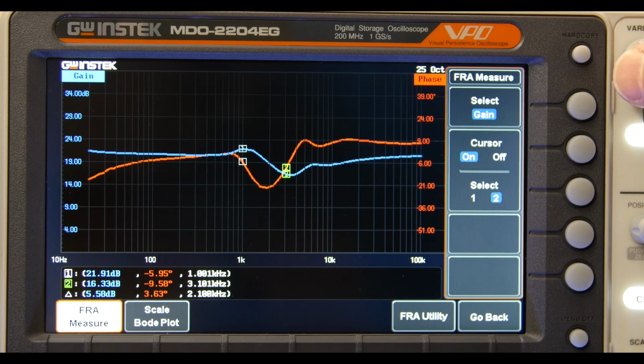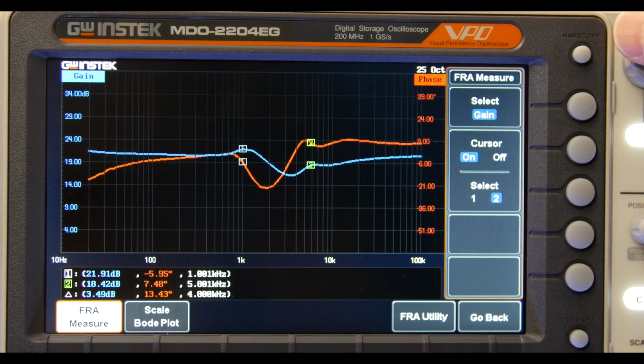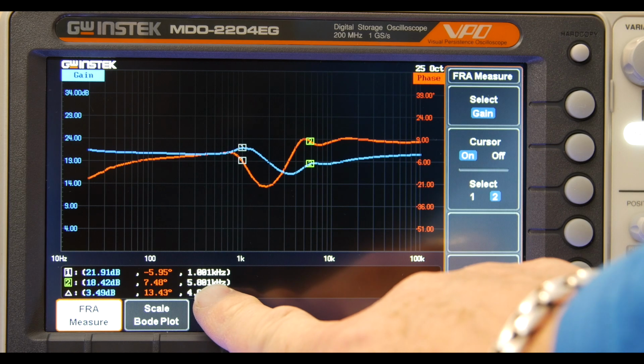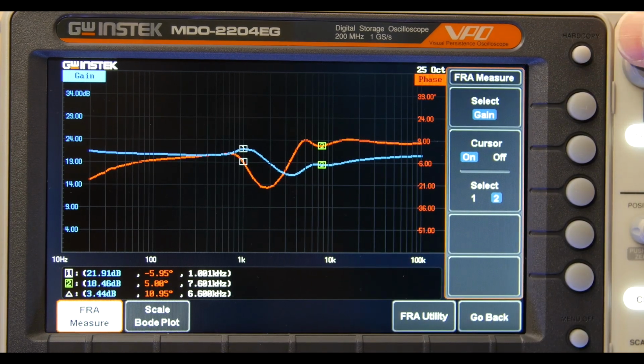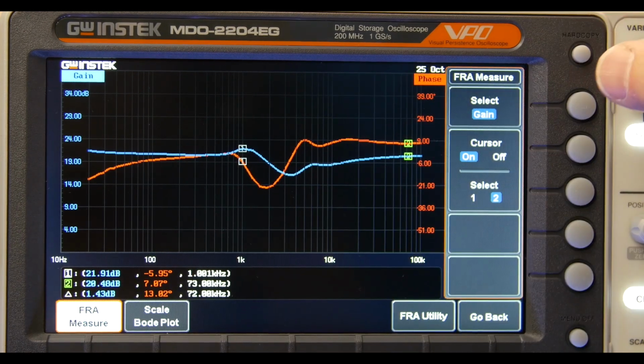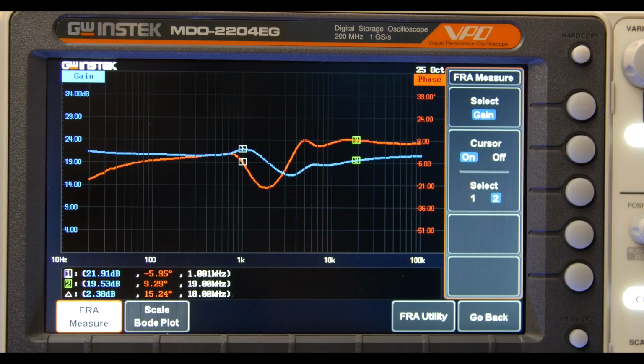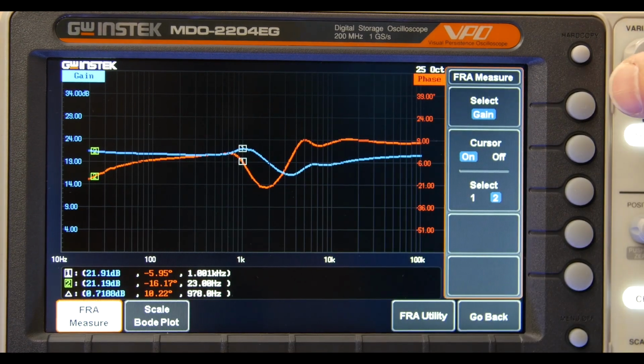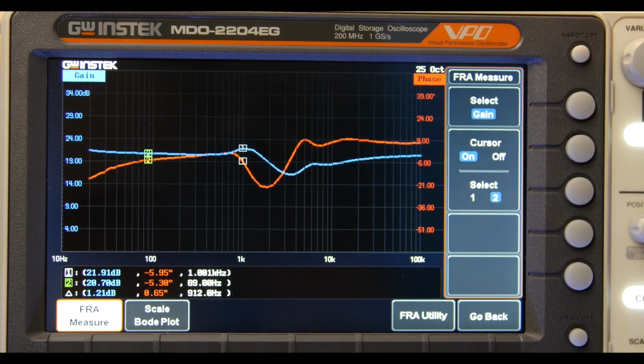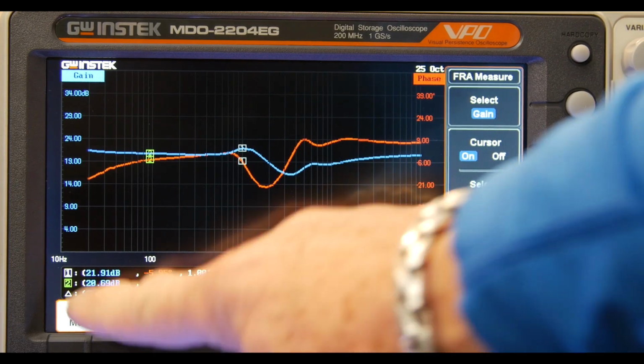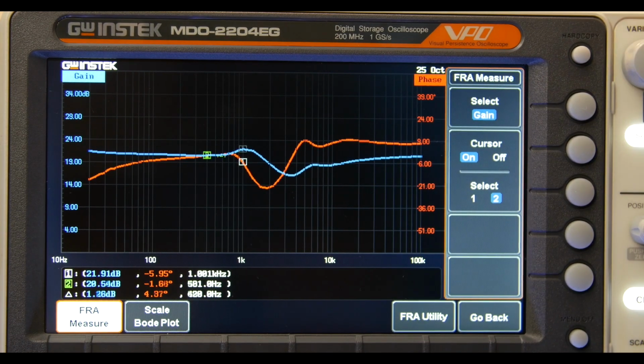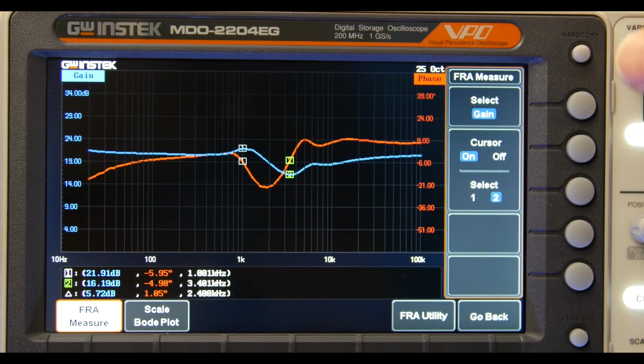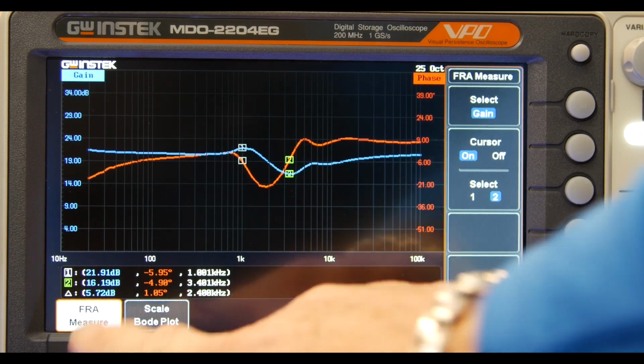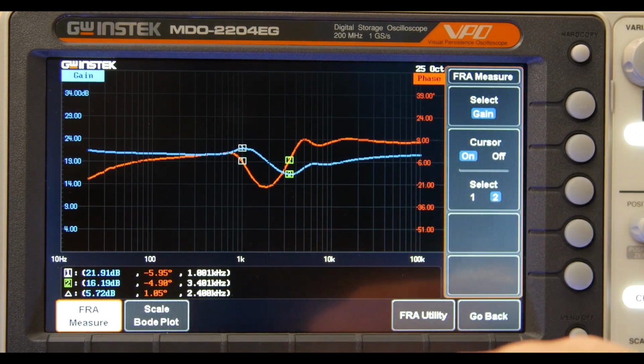So those are kind of the extremes. But if I take cursor number 2, well, right there at the bump where it straightened out, that's right around 5 kilohertz. And out here it's about 20.4 dB, and over here at the beginning is about 21.91 dB. So it's pretty flat through here. You can see the delta here between this one. So even between the extremes, the delta is about 5.7 dB and 1 degree.